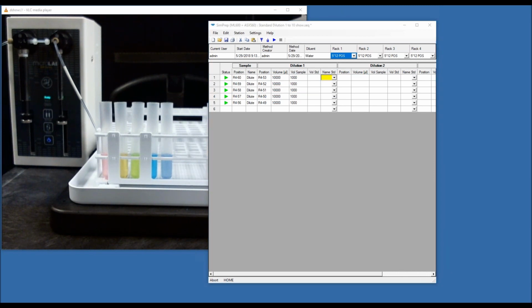I do have one here about the spike, or how did we do our carryover testing. I think this was covered, but just in case, I'll go through it one more time. The carryover study was done as a follow-up to our standard prep. So we did our calibration curve study and a carryover study side by side. We had the diluter system prep our calibration curve off of a 100 ppm stock solution, and we prepped the high standard last, at a 1 to 10 dilution, so a final concentration of 10 ppm. Directly after that was prepped, we prepared a blank just the same way as a 1 to 10 dilution.